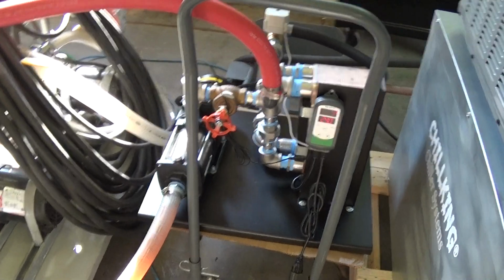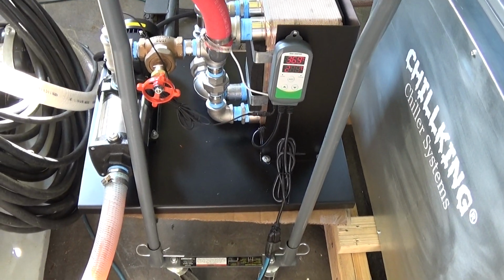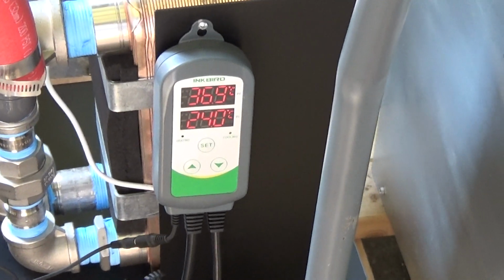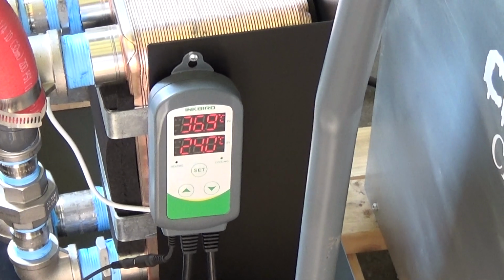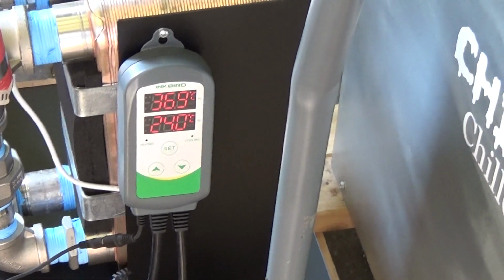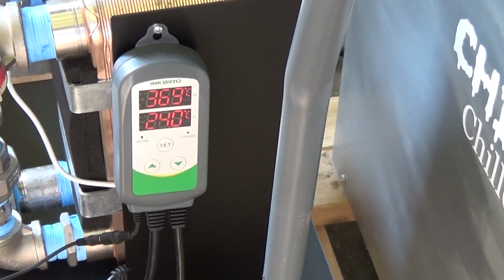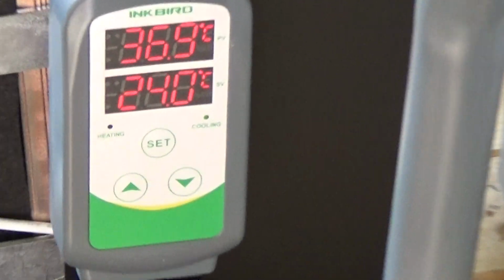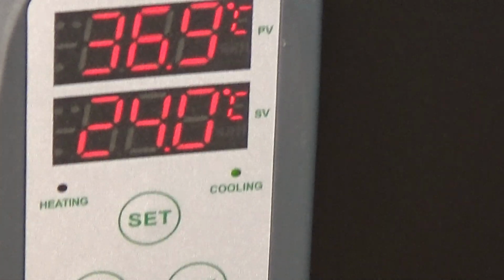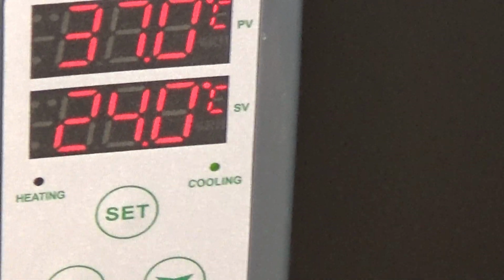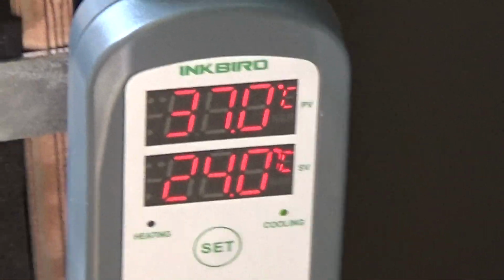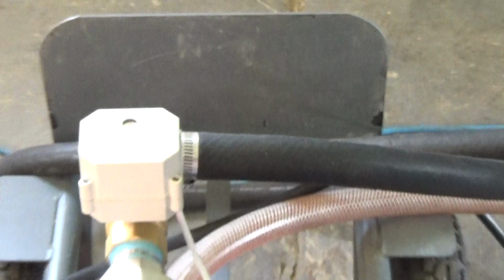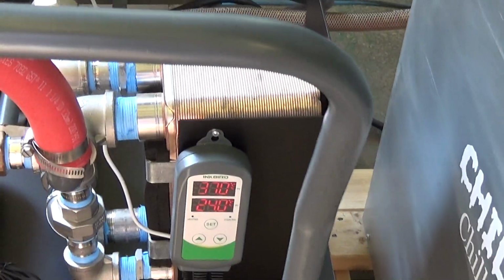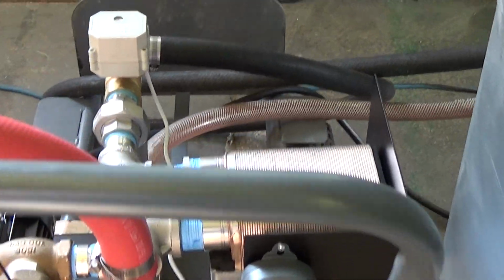Additionally, there's a requirement to have tighter tolerance control than what a typical air-cooled chiller can achieve. So for that reason, we have this Inkbird controller here, which is similar to what you would see on fermenters or a bright tank in a brewery, which when it's in centigrade mode can be programmed to a differential of 0.3 degrees C. So for example, here, with a 24 degree set point, when it gets up to 24.3 degrees, which is the tightest differential that it can do, then we will open up that motorized valve, thus introducing the chilled fluid into the glycol side of the heat exchanger. So that's going to just modulate back and forth based on the temperature of the process.